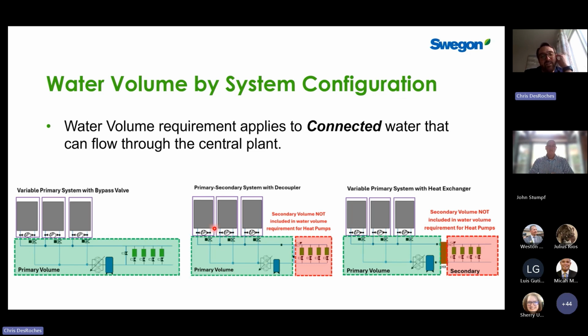When you look at a primary secondary system, or variable primary, variable secondary, or even a heat exchanger decoupling, what we would consider water volume for minimum water content purposes is the primary volume, because it's all about making sure that you have enough heat within the system for the units to complete defrost. So you don't necessarily have, under all circumstances, full flow on the secondary. There are different strategies that can be implemented. It's not so easy to provide a black and white rule. It really depends on the application and a variety of conditions that we're concerned about designing to ensure that we're protected with enough water volume.